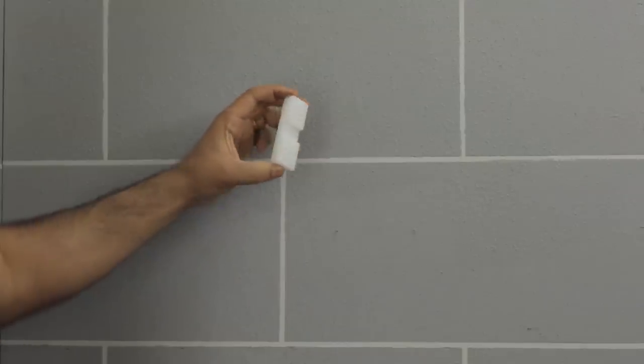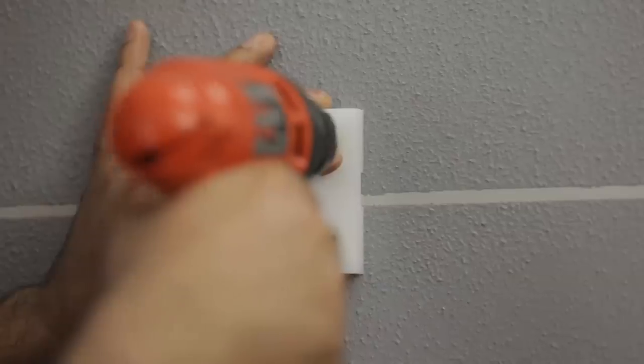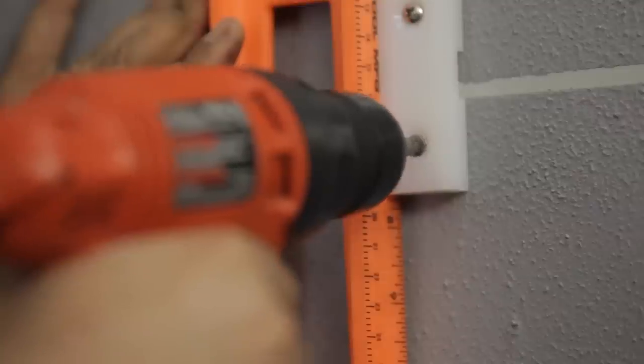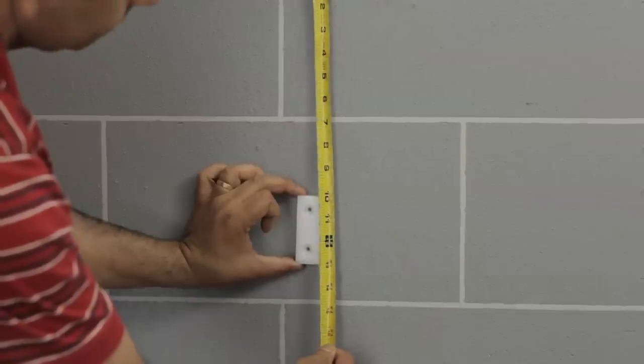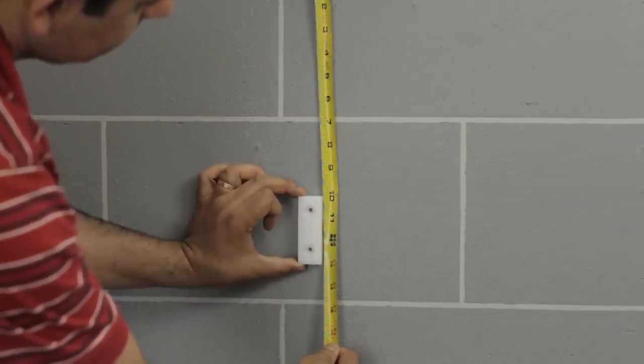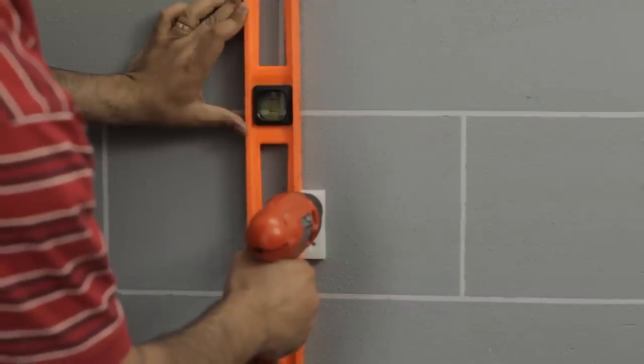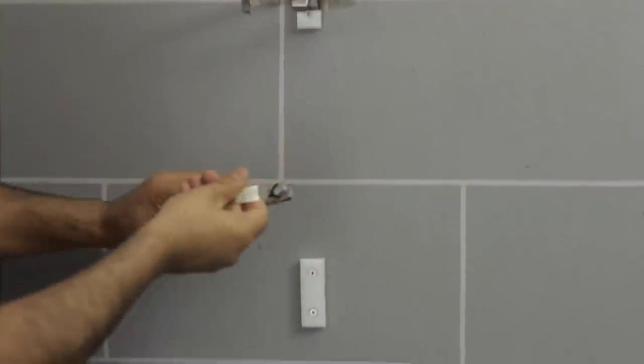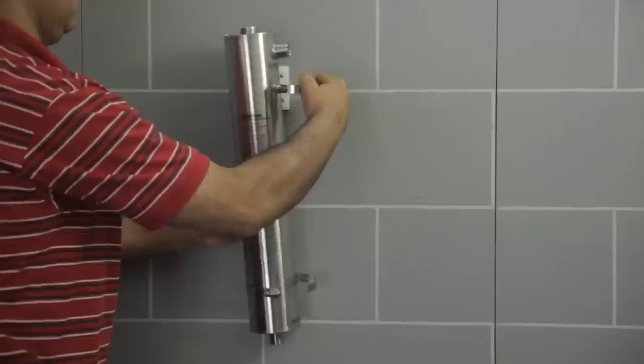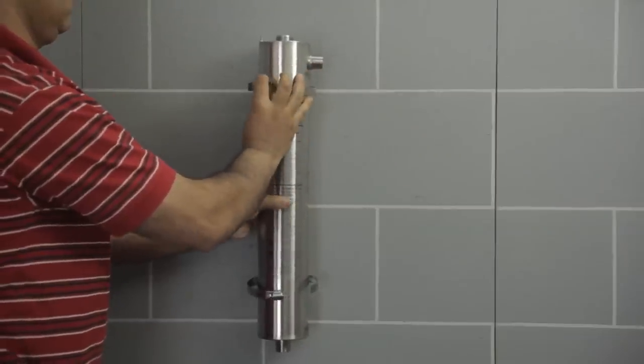Select a location where service or lamp replacements can be easily done. Screw a mounting base to the wall, and using a level, align the second mounting base about 11 to 12 inches apart. Slide the mounting clamps onto the bases in opposite directions. Mount the chamber on the bases and tighten the clamps to secure it.